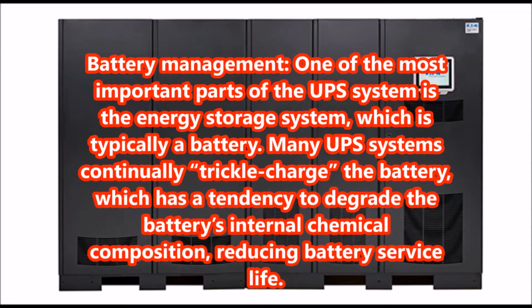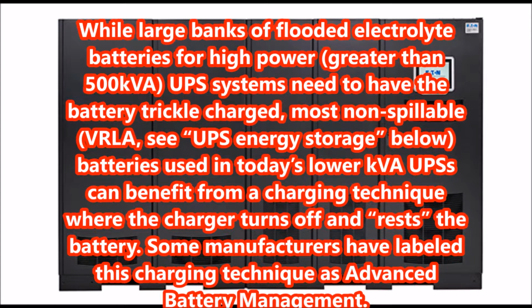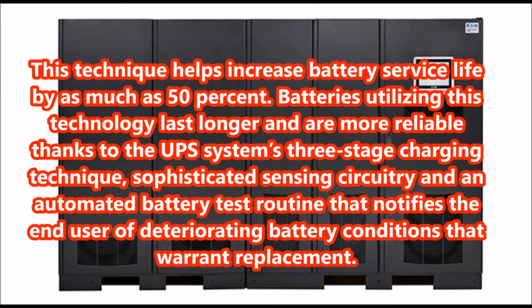Battery management. One of the most important parts of the UPS system is the energy storage system, which is typically a battery. Many UPS systems continually trickle charge the battery, which has a tendency to degrade the battery's internal chemical composition, reducing battery service life. Large banks of flooded electrolyte batteries for high power greater than 500 kVA UPS systems need to have the battery trickle charged. Most non-spillable batteries used in today's lower kVA UPSs can benefit from a charging technique where the charger turns off and rests the battery. Some manufacturers have labeled this charging technique as advanced battery management. This technique helps increase battery service life by as much as 50%.